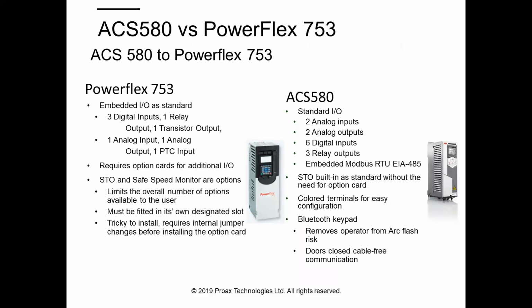So in this slide, I want to talk about the IOs comparison between 580 and PowerFlex. As I mentioned before, 580 has two analog outputs, six digital inputs, three relay outputs. It comes with Modbus built-in RTU, and we have STO built in, also color terminal and the Bluetooth keypad, which gives kind of cable-free communication, removing that arc flash risk.